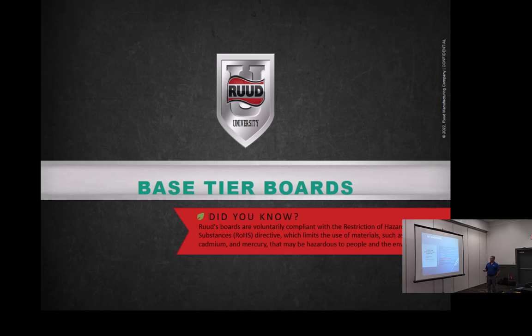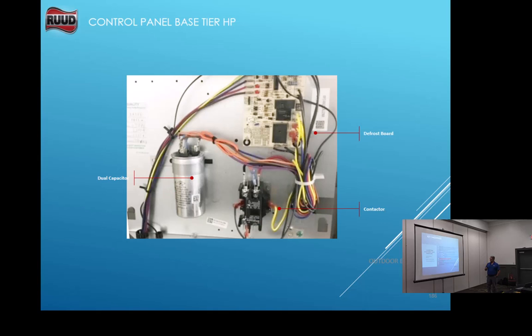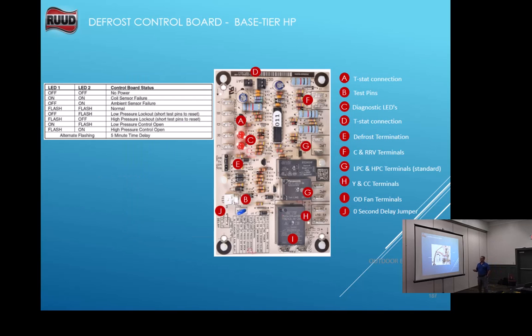We're going to talk about our control panel for our base tier heat pumps. That has not changed. Same board. No difference, okay? Still has our pressures on here, our little chart on here as to what our flash codes are for normal operation, ambient sensor, off and on, what our flash codes are. This board has not changed in the last couple of years. Same board, okay?